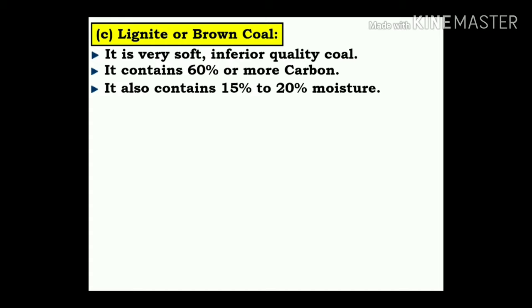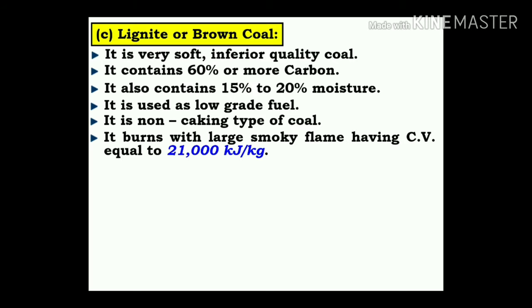Lignite or brown coal: it is very soft, inferior quality coal. It contains 60% or more carbon and also 15% to 20% moisture. It is used as a low-grade fuel. It is a non-caking type of coal and burns with a large smoky flame, having a calorific value equal to 21,000 kJ/kg.